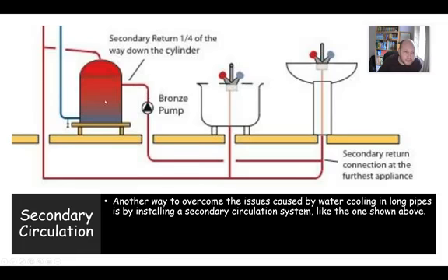This water is going to be probably 50, 55 degrees, possibly as much as 60 degrees, circulating around here all the time, which means that as soon as you open this tap, the only bit of coolish water is this meter going up to the appliance. So you get hot water almost straight away, which is great.